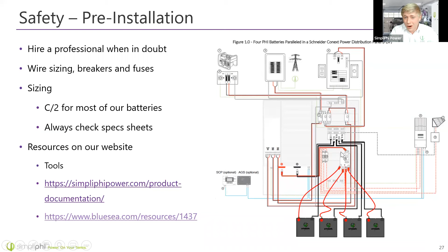Now, there's other considerations, of course, that go into planning and installation, but I don't want to go too in depth in this video. We have several other videos about that. But one other thing I want to point out briefly is that look at the detail of this wiring diagram. I've actually pulled this off of one of our installation guides, so we do some of the work for you. However, your installation is likely going to differ at least somewhat from ours. So what I encourage everybody to do is make a single line diagram and then also make a 3-line diagram or 2-line, whatever suits your application, and actually show each connection, right? So make sure you're not forgetting how many lugs you need. For example, the terminal post sizing, how many lugs you can land on one terminal block. All those are important, and those details are kind of going to be missed in some single line diagrams.